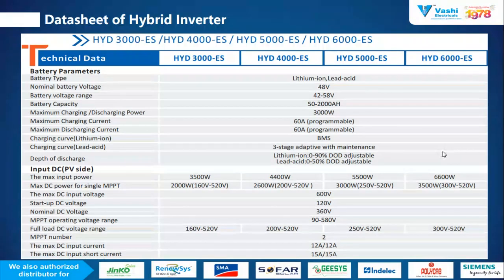So hybrid inverters have a maximum of 600 volt DC voltage capacity, and they have 2 MPPT connections on the DC side. The main topic is the depth of discharge. For lithium-ion batteries it is mentioned here as 90%, and for lead acid batteries it is 50%. But when considering lithium-ion or lead acid batteries, as I said, you have to submit the technical data sheet if you are using local batteries. According to that, we have to set certain parameters in the hybrid inverter, so that can be adjustable. That's why DOD adjustable is written here. That is also the charging curve for the lithium ion as well as the lead acid batteries, so it can be adjustable.